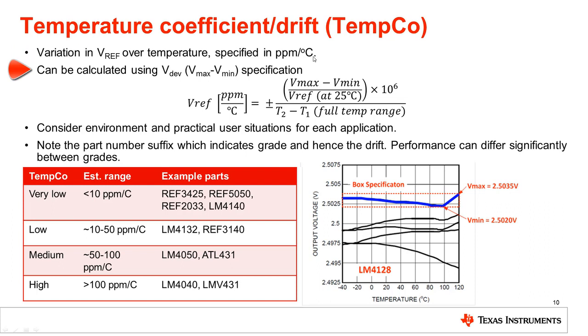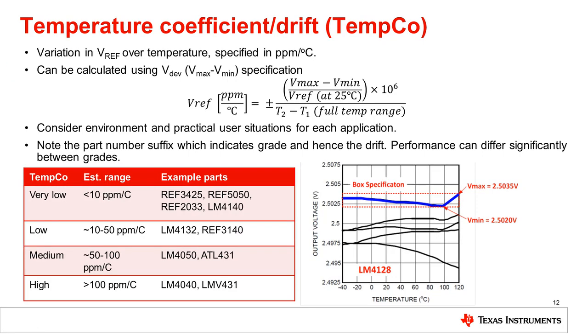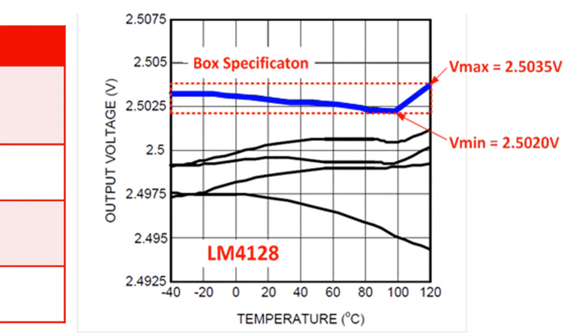We can calculate the coefficient by using the full temperature range and obtaining the maximum and minimum reference voltages, as can be seen in the formula. The graph on the right shows us that the temperature drift is non-linear, and that instantaneous drift may be higher in some areas than in others. Thus, the temperature coefficient can be thought of as the average drift across the entire temperature range.